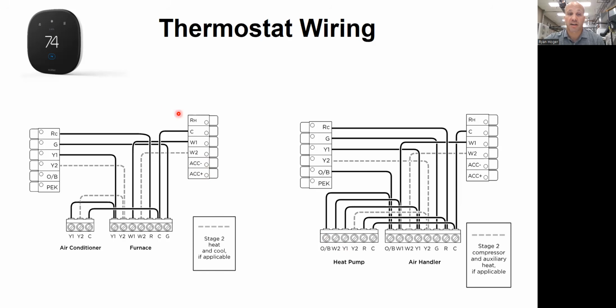On the straight cooling system, I didn't have to worry about that because it didn't have a reversing valve. Now I got a reversing valve, and the thermostat is the one whose job is to tell it that. It means I need an extra wire from the thermostat to the air handler, and it means I need an extra wire from the air handler to piggyback out to the condensing unit outside, or excuse me, the heat pump outside. So now I have Y, C, and O/B going outside, 3 wires instead of just the 2 over here, right?